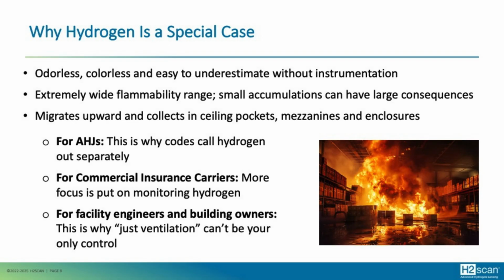We have seen many instances where ventilation systems are either not adequate or have failed because they are mechanical devices. This could be the louvers on the outside of a facility. It could be the fan doesn't maintain the correct airflow that it needs to maintain, or it could simply stop working. So while fans are your primary defense against hydrogen buildup, sensing should also be installed. And they can be installed together. Again, you can use sensing to activate fans or to activate additional fans or increase a facility's HVAC system to maximum output so that it moves air around so that hydrogen doesn't have the chance to accumulate into an explosive mixture.